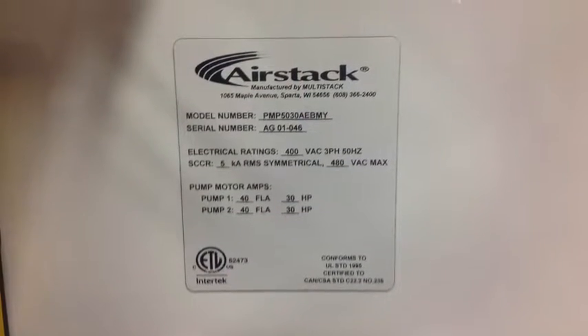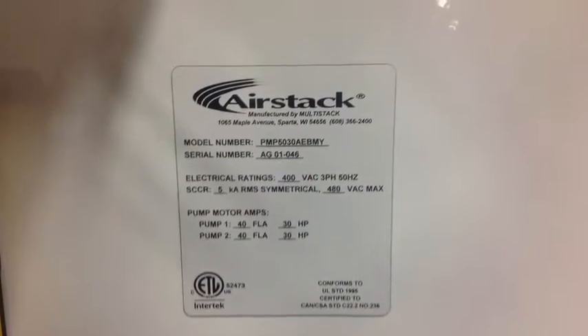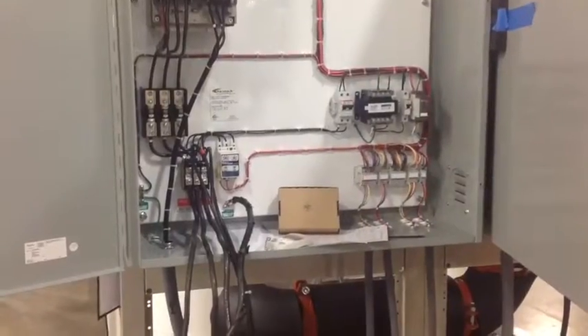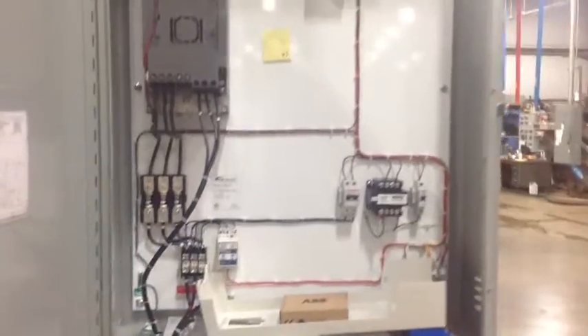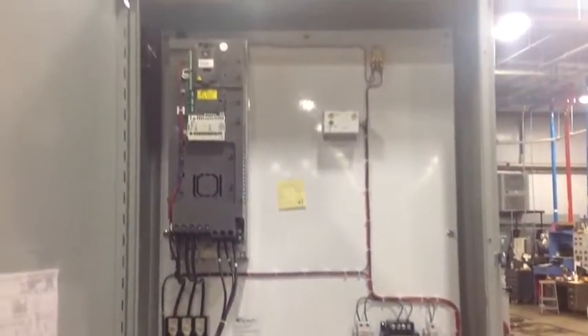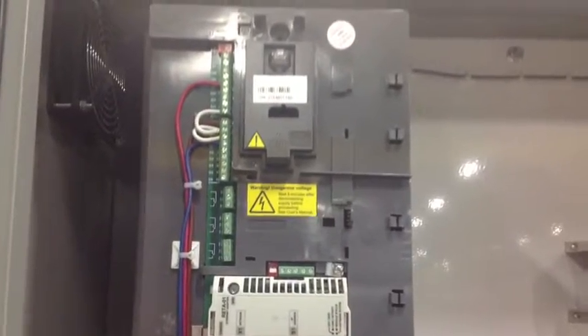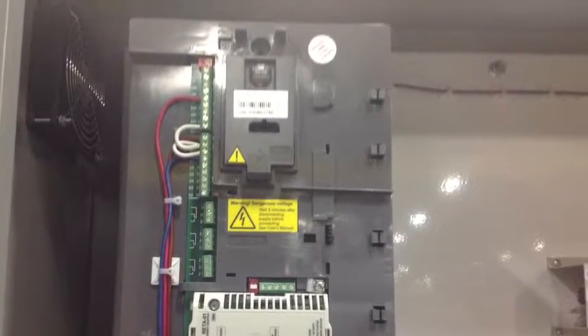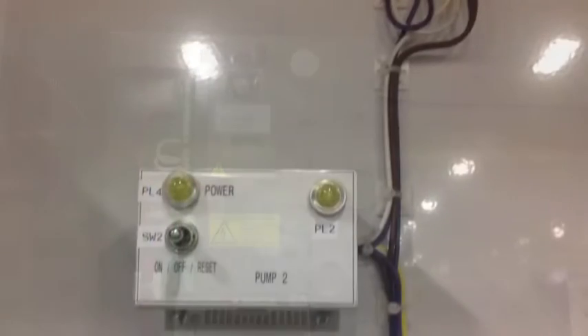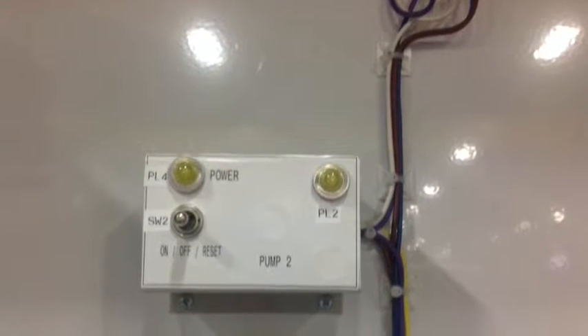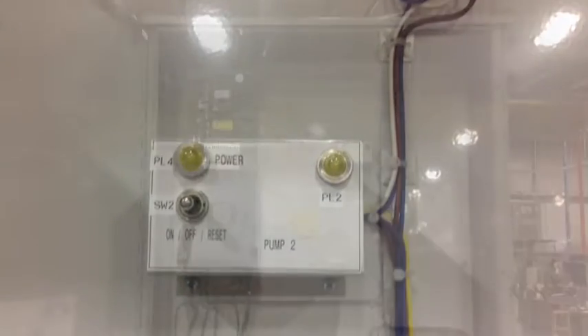Here's the serial number for the first pump. The pump cabinets also have a timer which automatically rotates the lead and lag pump. This can also be configured via the BACnet IP connection to each VFD through the building automation system. There are some close-up views now showing the variable frequency drive, the local start-stop switch which is found in each cabinet.